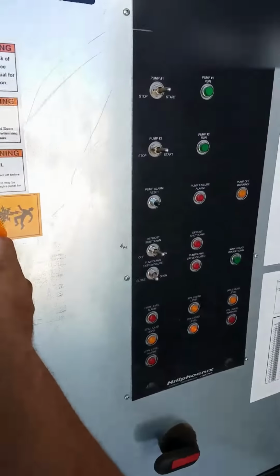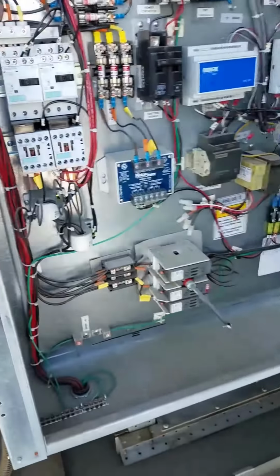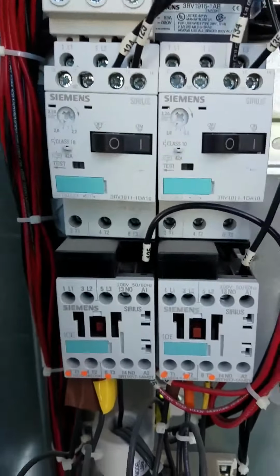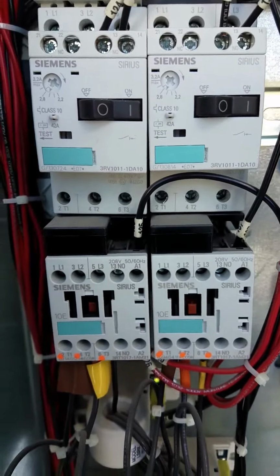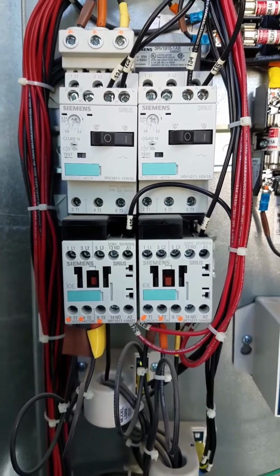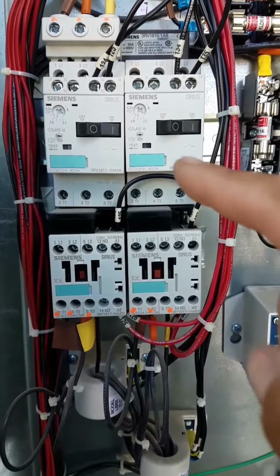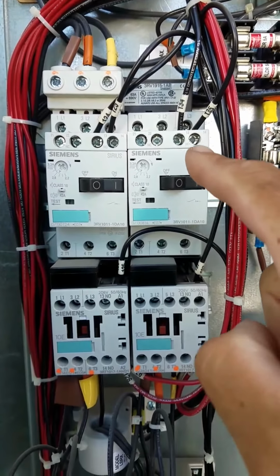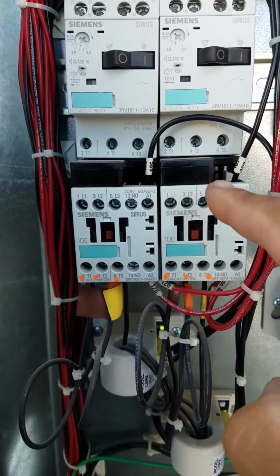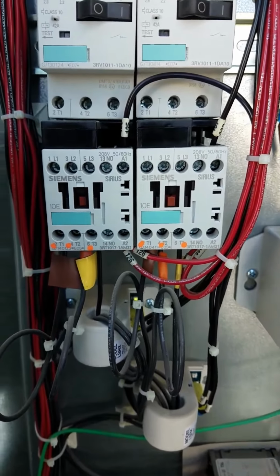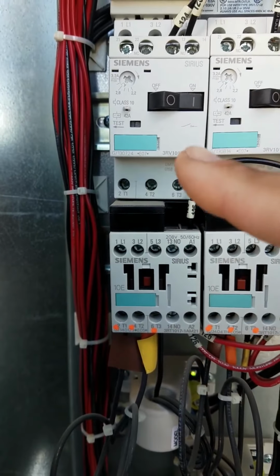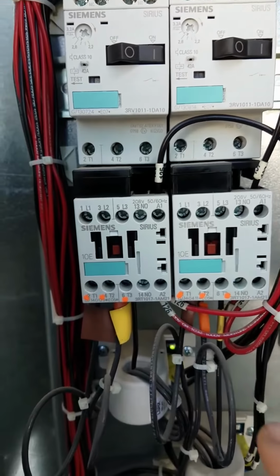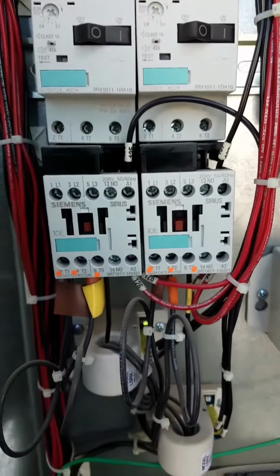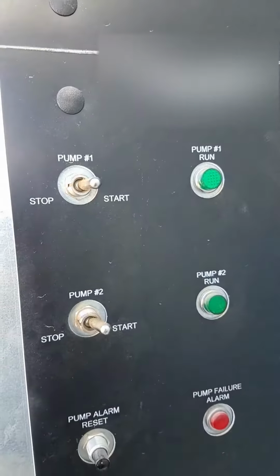Alright, what I found was I went into the pump panel, found the pump breakers and contactors. This is how they look. All the contacts up here were really loose on all the connections, so I just went ahead and tightened them all up. Did the same to pump 1. This is pump 2.